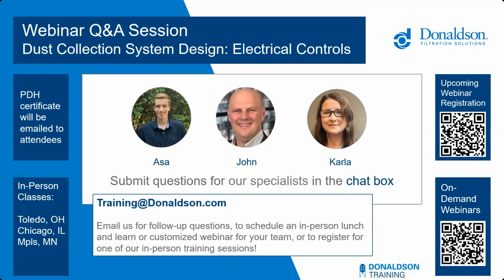On our newer systems, we do have that option if you would like to, but that is a custom solution. If you want to take some readings of the actual CFM or the velocity, you certainly can do that. But as a very cost-effective alternative and a way to just have a simplified solution, it's simply static pressure from the dirty plenum and meeting the window, if that makes sense.